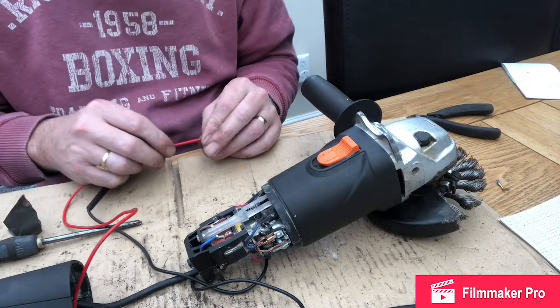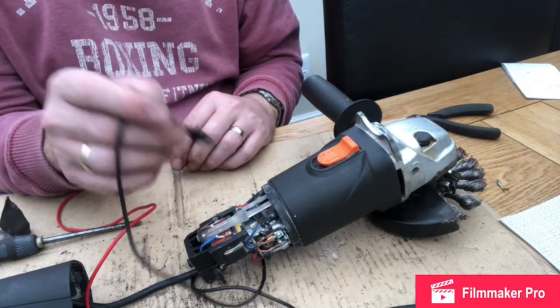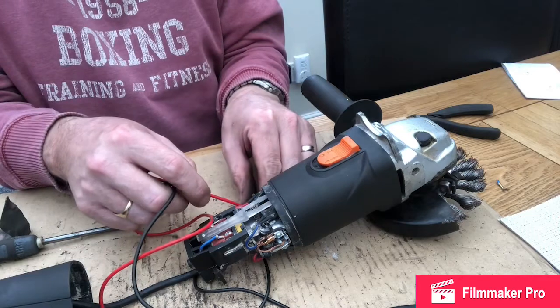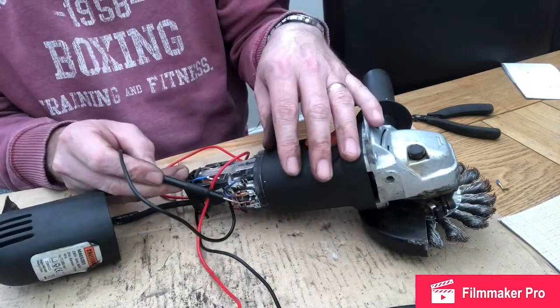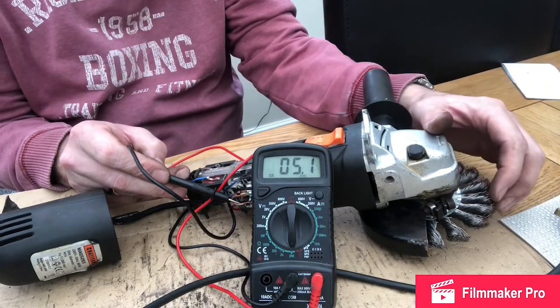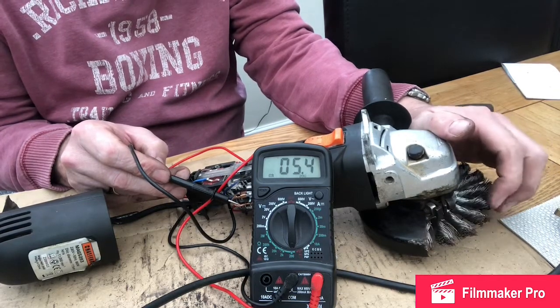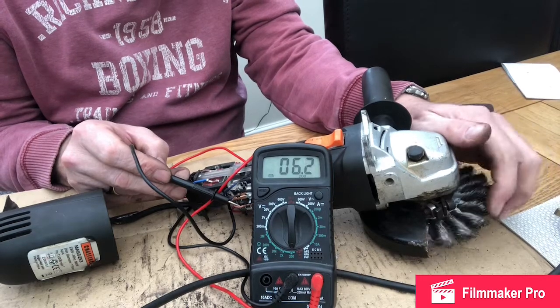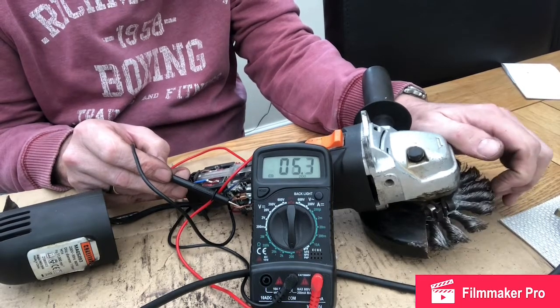One quick test you can do is to prove the coils in the commutator. As it turns it's energising pairs of coils, and the turning motion moves on to the next pair of coils. Connect your multimeter on ohms to the brushes. You can see we have a reading, and if I turn it we move on to the next pair of coils. We now know the brushes are making good contact with the commutator, and that's proved every pair of coils because we never once broke continuity.